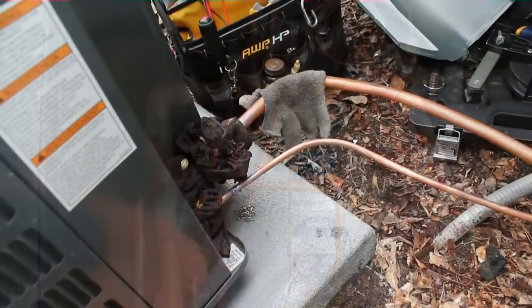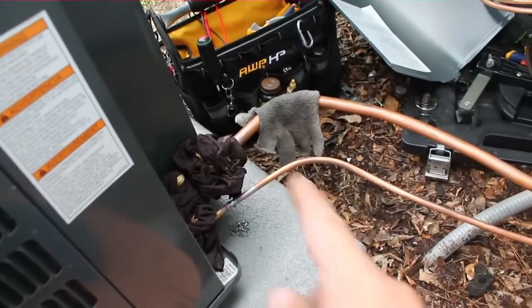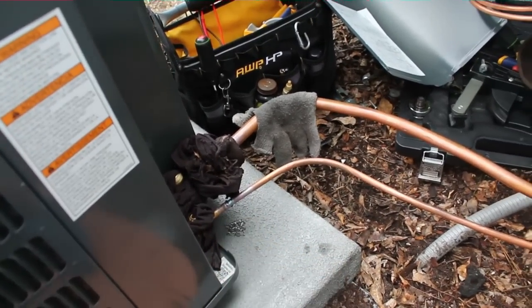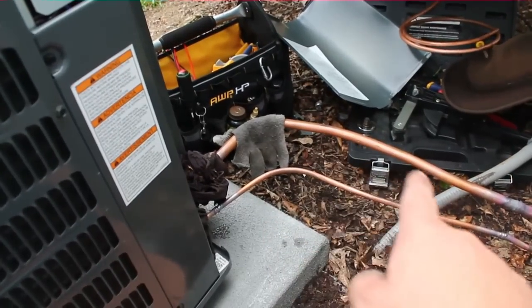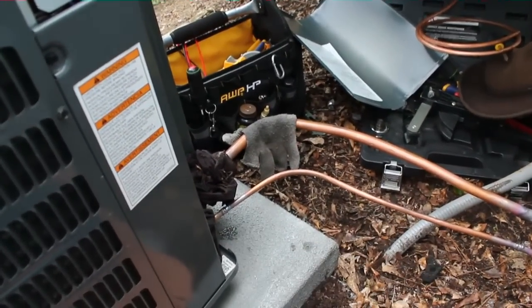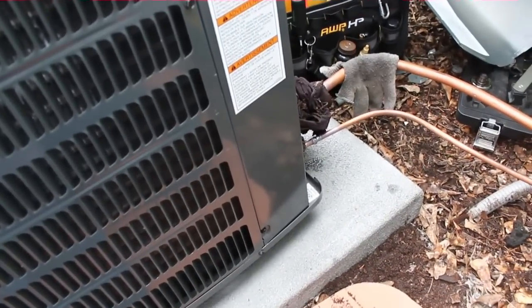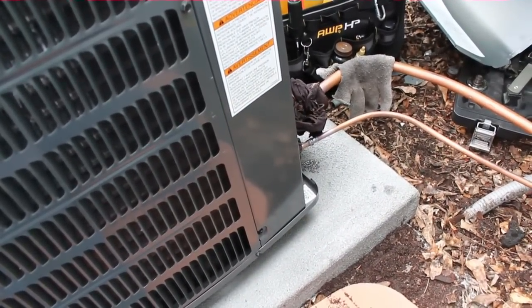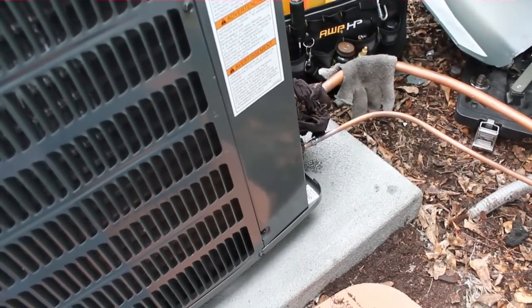Now I'm heading outside. I finished brazing up the outdoor unit. Got a couple of rags wrapping the service valves. Brazed back to the original line set there. Do a little bit of straightening through here. Put our insulation on once the pressure test is done. Because this customer bought a scratch and dent unit, I will be making a repair here as well. The outdoor coil came from the factory with a leak in it, so we are going to repair that leak and then pressure test the entire system.